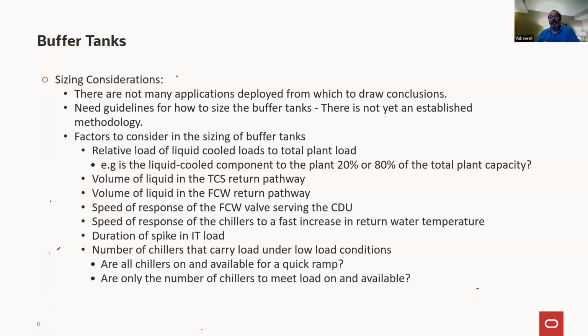Yeah, I agree with that completely, and that's at the heart of that issue about how much of the load is actually liquid cooled, the load that goes to the plant, and the larger that load, the more easy it becomes to move that buffer tank out of the TCS loop, put it into the facility loop. And when you do that, it's a different metal, it's a different liquid, much easier to plan for it. For one thing, it doesn't have to be inside of the expensive data hall. It can be outside in the chiller yard. If you have air-cooled chillers, it can be in a mechanical room at the side of the building, and it can be much, much bigger.